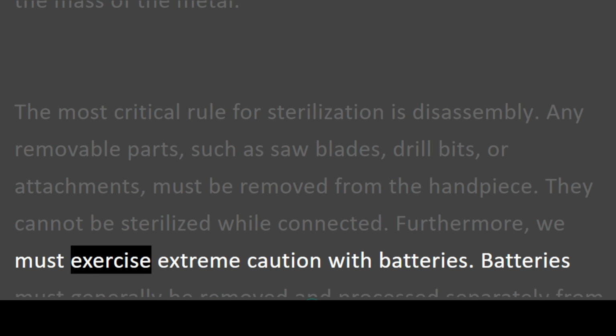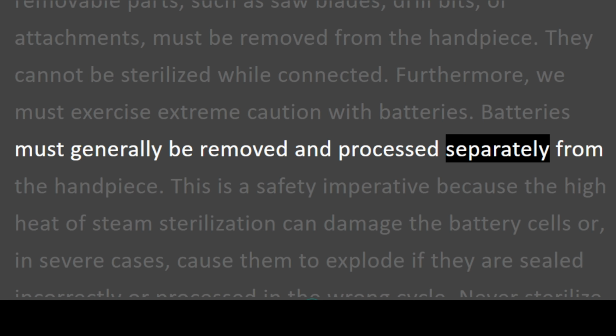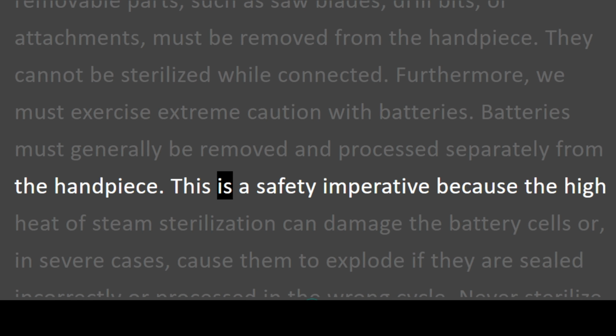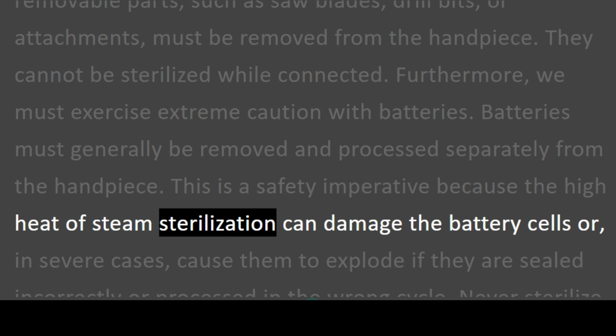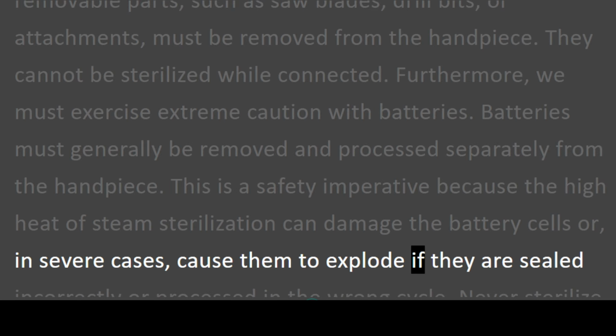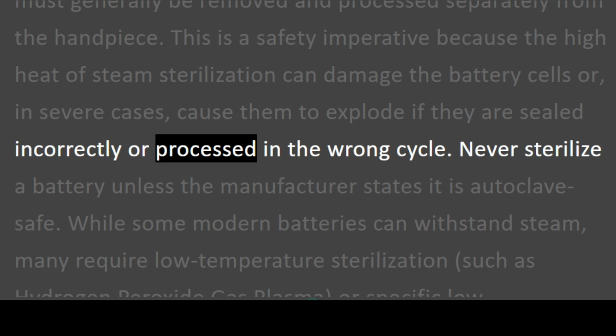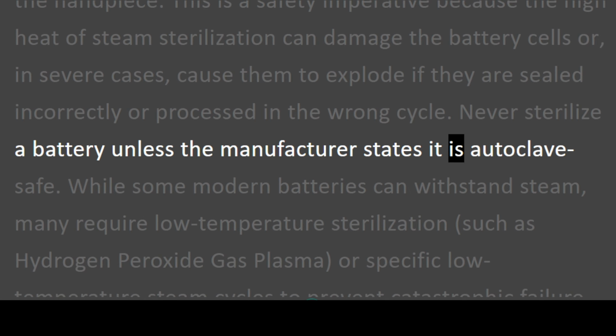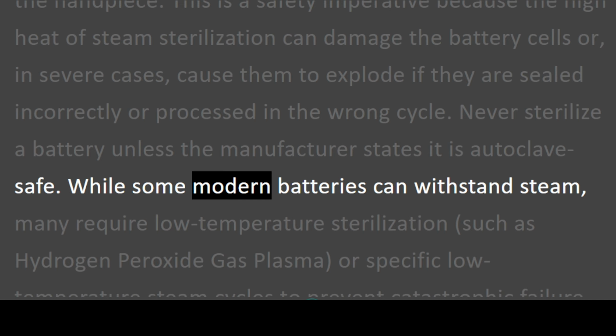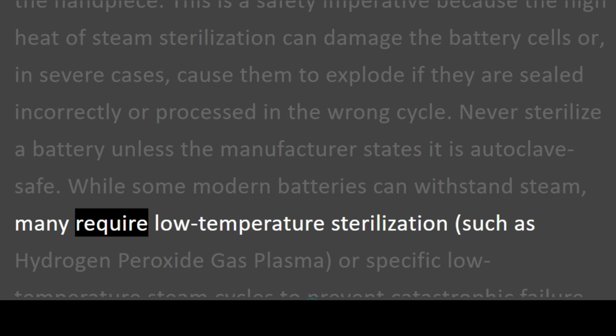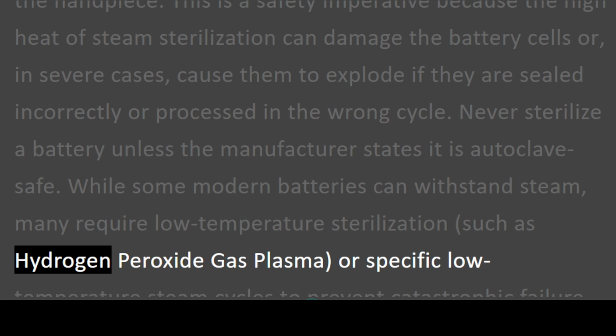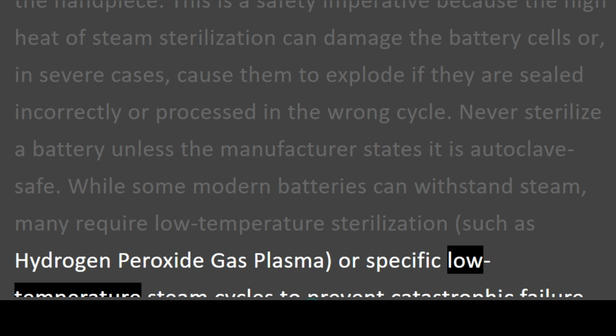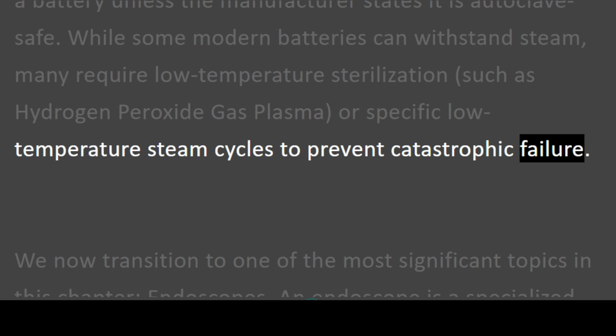Furthermore, we must exercise extreme caution with batteries. Batteries must generally be removed and processed separately from the handpiece. This is a safety imperative because the high heat of steam sterilization can damage the battery cells or, in severe cases, cause them to explode if they are sealed incorrectly or processed in the wrong cycle. Never sterilize a battery unless the manufacturer states it is autoclave safe. While some modern batteries can withstand steam, many require low-temperature sterilization, such as hydrogen peroxide gas plasma, or specific low-temperature steam cycles to prevent catastrophic failure.